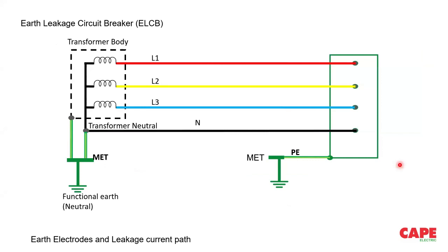Now, in earlier days, we were using a device called ELCB, earth leakage circuit breaker. Nowadays, these circuit breakers are not much available in the market. I think it is not at all available in the market nowadays. But it is interesting to understand the method of operation of this particular device, because we are talking about automatic disconnection, how to ensure that your device is tripping and how to get shock protection by this protective measure.